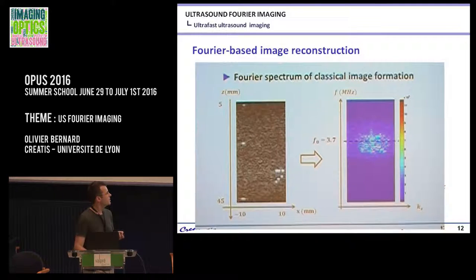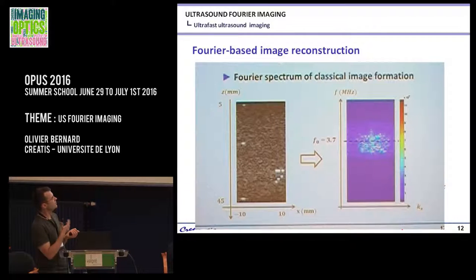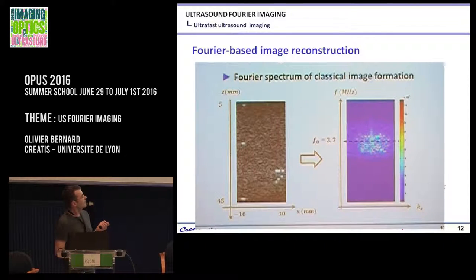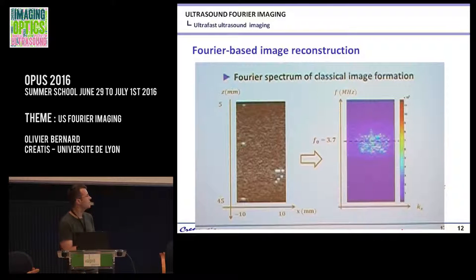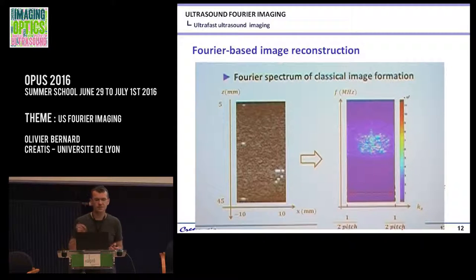With this Fourier spectrum, there are very strong properties. Here, Z is linked to time and X is the lateral dimension. If you do the 2D Fourier transform, you have KX and either F or KZ using the relation between KZ and F. Along the F axis, the spectrum is centered at the central frequency of your probe — for example, 3.7 MHz. The bandwidth, the spectral content along F, is directly linked to the bandwidth of the probe. Along KX, you are limited by the pitch, the distance between two elements.